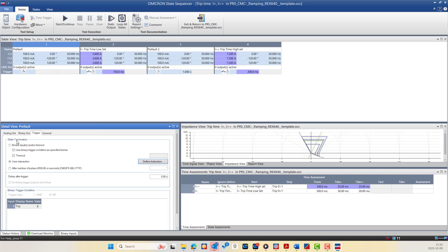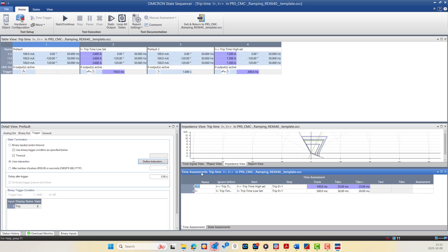You also have the Binary Input trigger condition, where the state will end when a specific binary condition is met, for example when the relay issues a trip signal. There is also Timeout, where the state automatically ends after a defined time has elapsed. Or you can use a combination of both — binary input plus time — so the state ends either when the binary condition occurs or when the maximum time expires, whichever happens first. This flexible triggering system enables precise control over the test sequence.